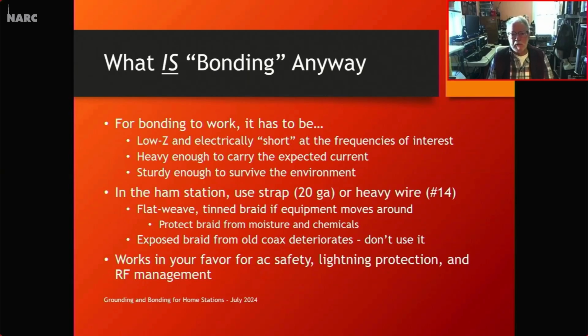If you have to use a braid, for example, your equipment is moving around, you want to roll something in and out or pull it in and out of where it's installed, use the flat weave tinned braid. You've got to protect that braid from moisture and chemicals. Don't ever use it where it's going to get wet or dirty or get nasty chemicals on it, because as soon as you do, it begins to oxidize. And once it begins to oxidize and develop that coating on the little wires, it no longer acts as a single conductor. It can, first of all, start to exhibit some serious resistance and impedance, and it also generates noise where those nonlinear contacts were made between wires.